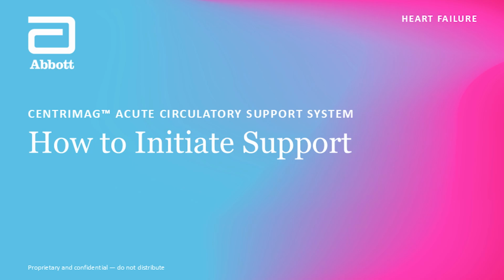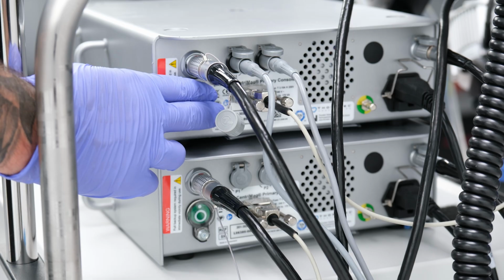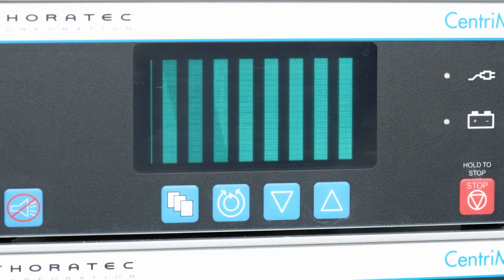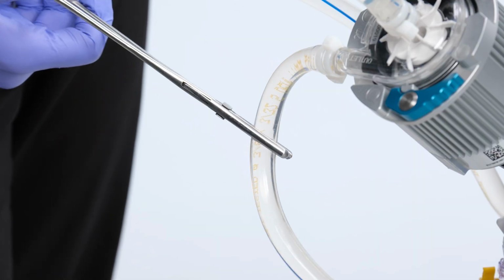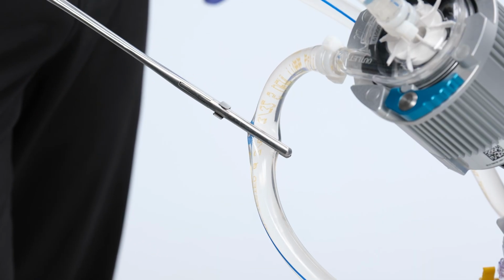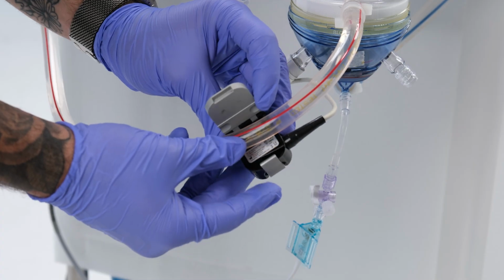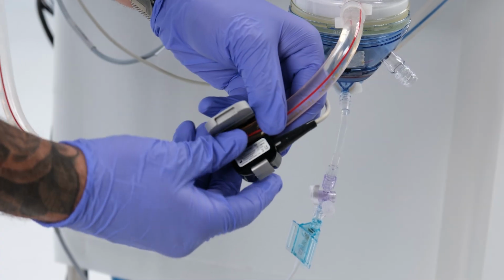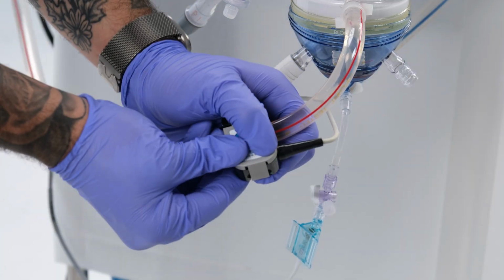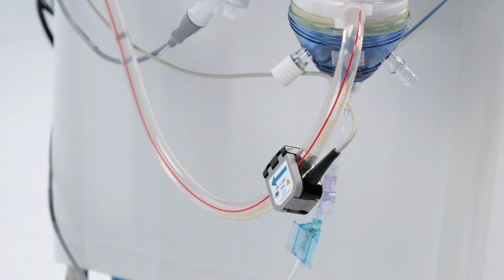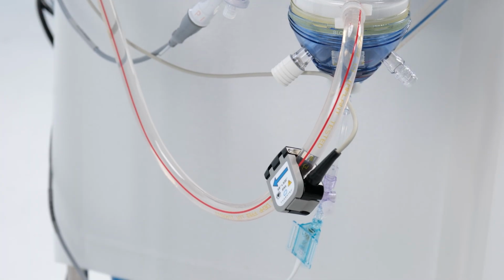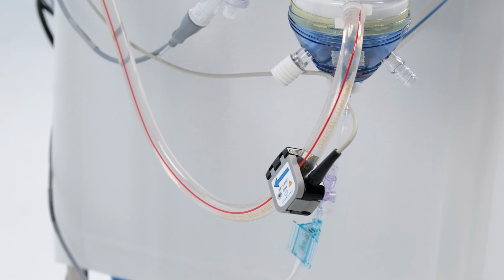How to initiate support. First, power on the CentriMag console. Ensure arterial tubing is clamped to prevent any backflow from the patient. Place the flow probe on the tubing distal to the pump with the arrow pointing in the direction of the blood flow. The flow probe does not need to be calibrated and does not need ultrasound jelly.